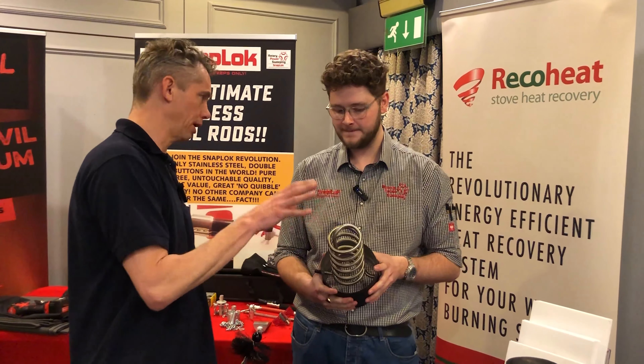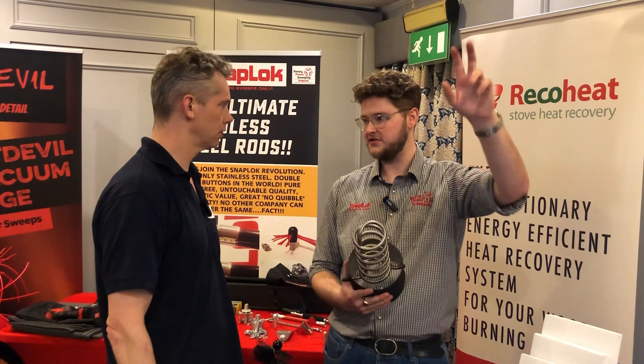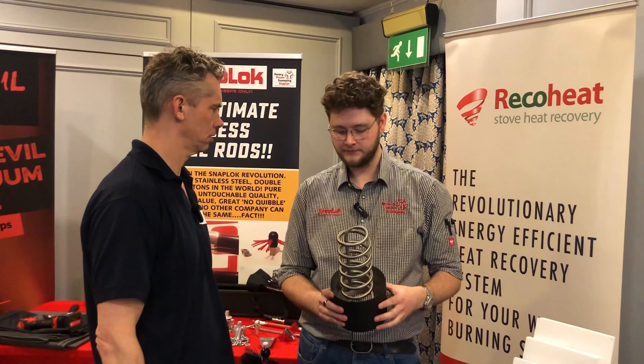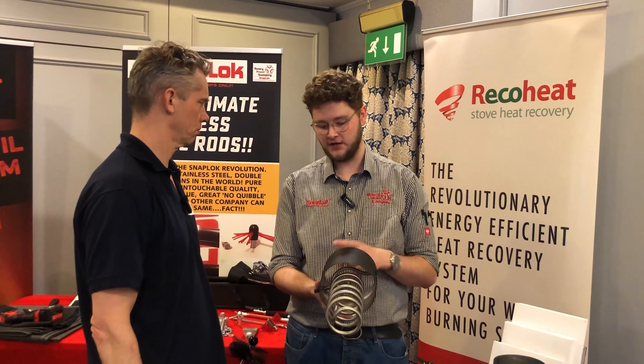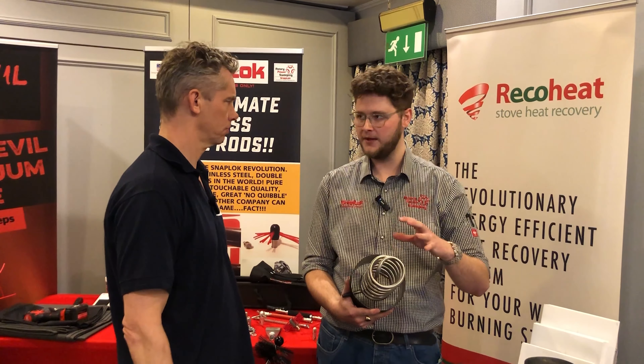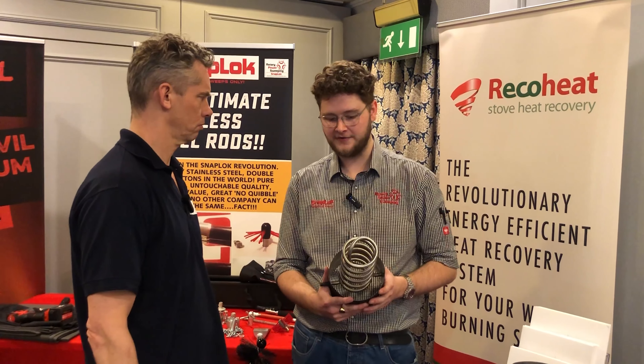So you'd clean the coil with the mole, then put a whip through there. Or you could just continue with the mole going up through the rest of the chimney and clean the rest. There are multiple ways of doing it — it just depends on the size really. Just for the spiral bit, you could potentially go slightly oversize, and then put the right brush up after that.